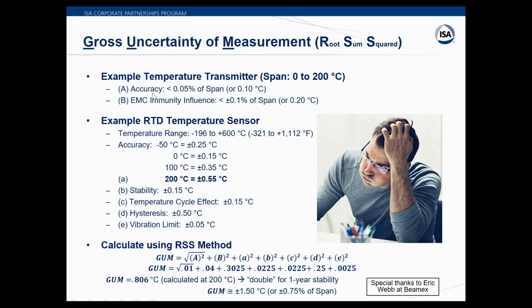So one of the things I like to say about accuracy, it's really kind of an off-the-shelf number. It's there the day it was tested. And then remember on the earlier slide, what was the reference standard that established this number? Is it accurate to a tenth of a degree C? That's another important component. So this instrument is spanned to 200 degrees C in this example. So if we take 0.05% times 200, we get this number, the tenth, and here this is double. So if we take 0.1% times 200, now we've got an additional 0.2 degrees.